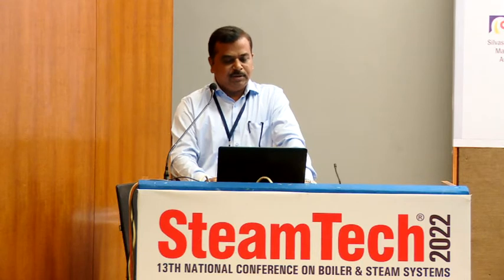So as I said, we have reduced energy consumption by 9.8% year on year. So this is our energy conservation journey. Our project on energy conservation, particularly condensate recovery, aims to harness all the waste heat from the compressor, effluent, condensate heat recovery and flash steam, which adds a value of 8 crores per annum in savings.